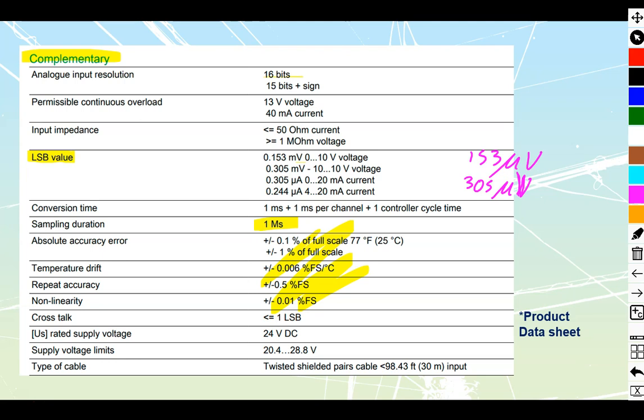Then we're going to go to this section where it tells us about the rated supply voltage. Now the rated supply voltage is not the 0 to 10 volt. This is to power up the card because the card itself needs to have power brought into it. 24 volts rated, it could go down as low as 20.4 and up to as high as 28.8. They tell us that the cabling should be kept to under 30 meters of twisted shielded pair cable.